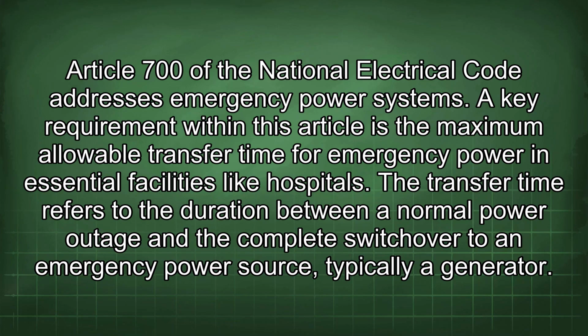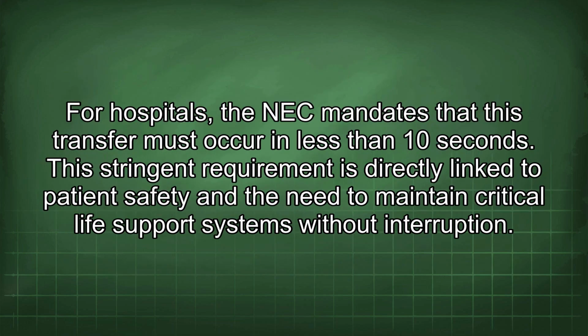Article 700 of the National Electrical Code addresses emergency power systems. A key requirement within this article is the maximum allowable transfer time for emergency power in essential facilities like hospitals. The transfer time refers to the duration between a normal power outage and the complete switchover to an emergency power source, typically a generator. For hospitals, the NEC mandates that this transfer must occur in less than 10 seconds.